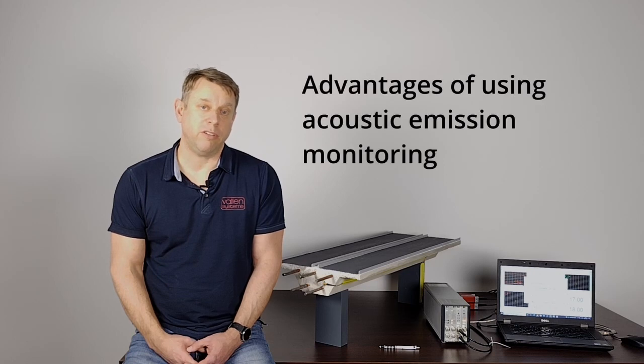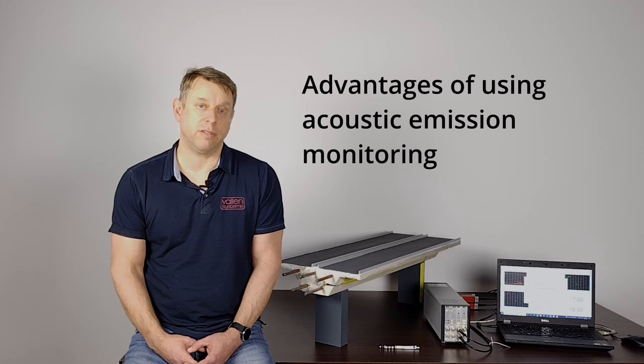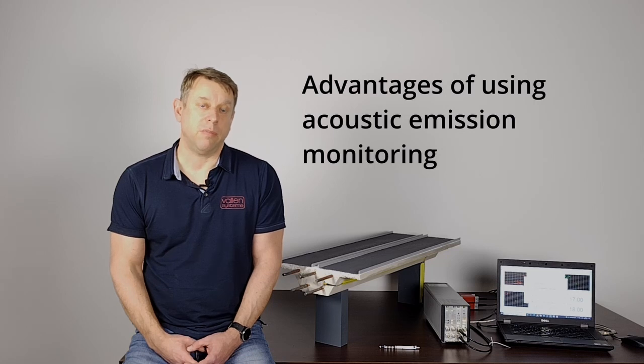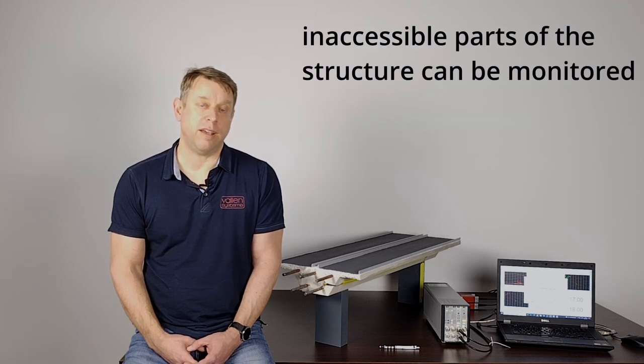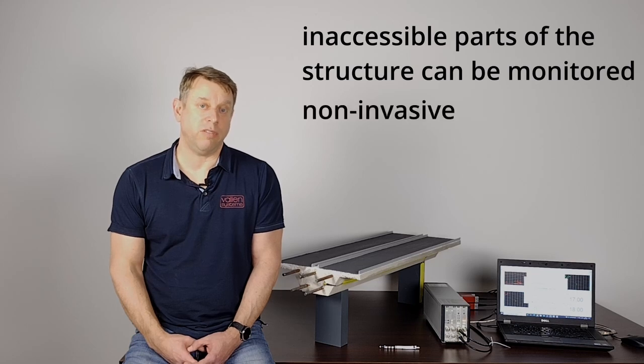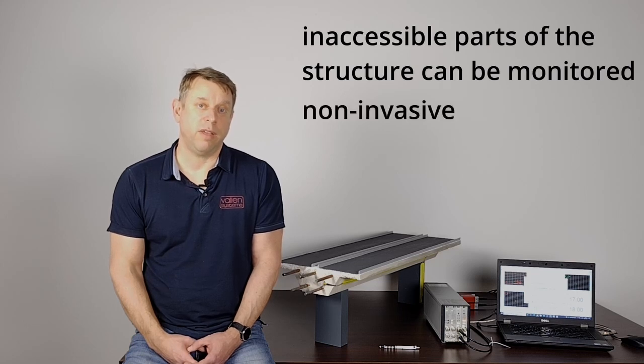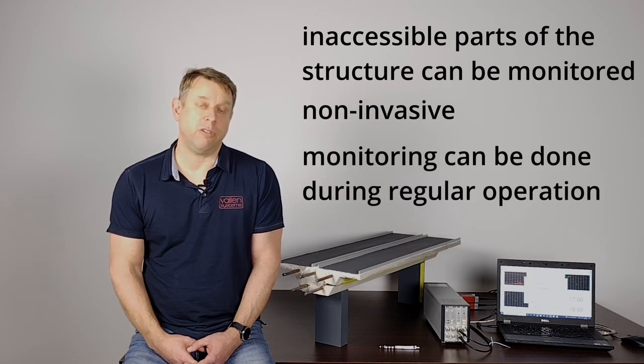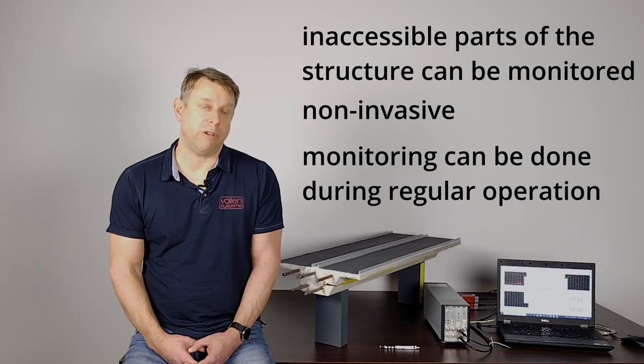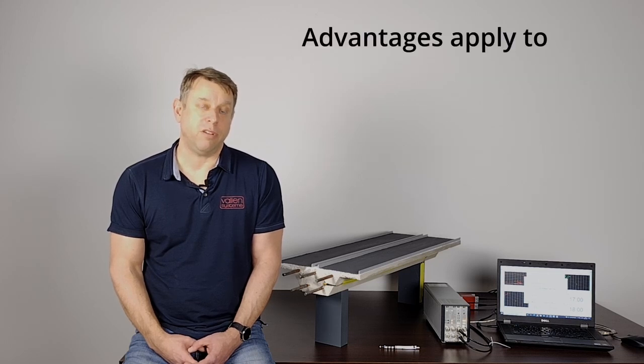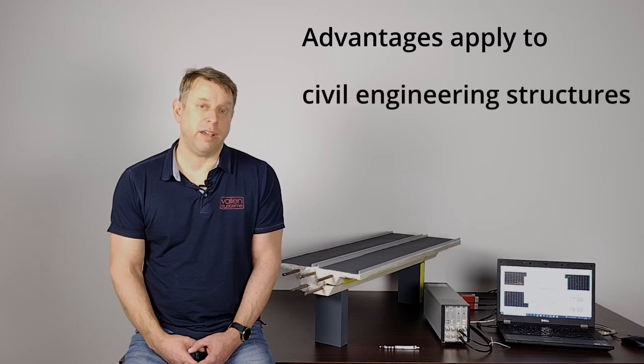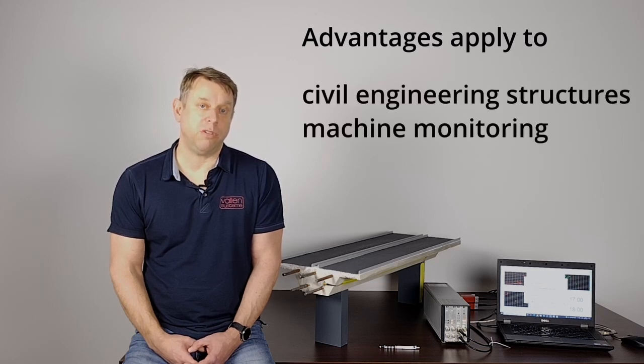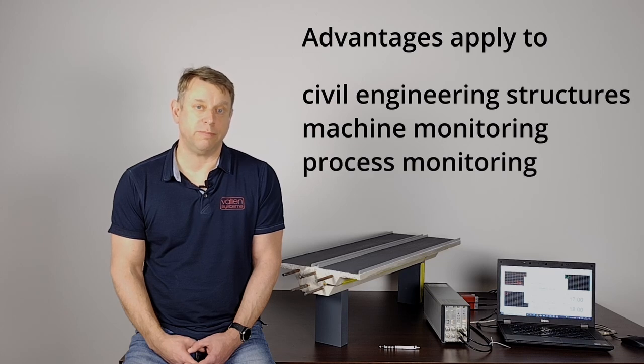Inherent advantages make acoustic emission extremely suitable for monitoring tasks. The most important advantages are inaccessible sites of a structure can be monitored, it's non-invasive and monitoring can be done during regular operation of the structure. This is valid not only for bridge monitoring but for monitoring any kind of structure and even for applications like machine monitoring or process monitoring.